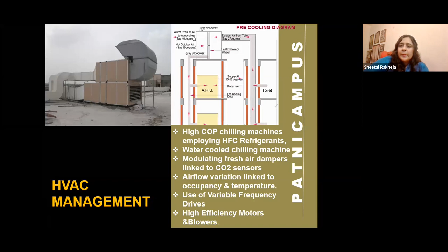You'll see most offices run air conditioning in these weathers too, but we didn't. We were just pumping in fresh air from outside, and we were pre-cooling that fresh air using a heat recovery wheel, which would cool the incoming outside air at the rooftop and then supply it to the various floors, instead of pumping fresh air to every AHU separately and cooling it, which would require much more energy.